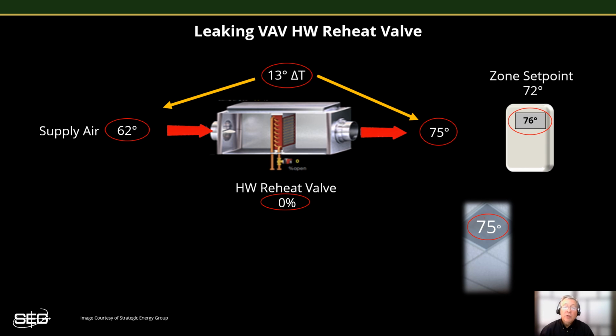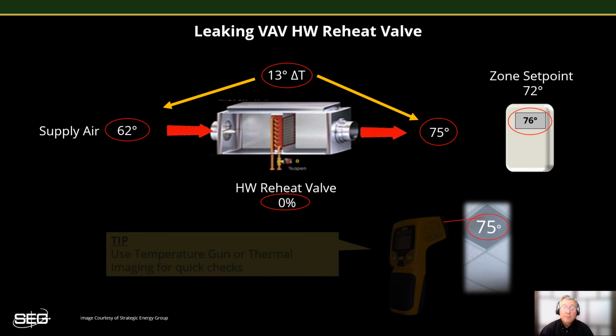Many buildings use terminal units with reheat coils to provide supplemental heat out at the zones. There's oftentimes hundreds of these in a typical building, so chances of one or more leaking by are pretty good. If you have hot water reheat valves, be on the lookout for the zones that are persistently stuffy, and in particular, those that frequently suffer from insufficient cooling ability on warm days. These are common symptoms of leaky reheat valves, and just a little bit of leak by can quickly eat up the cooling capacity of a terminal unit, causing persistent comfort complaints.